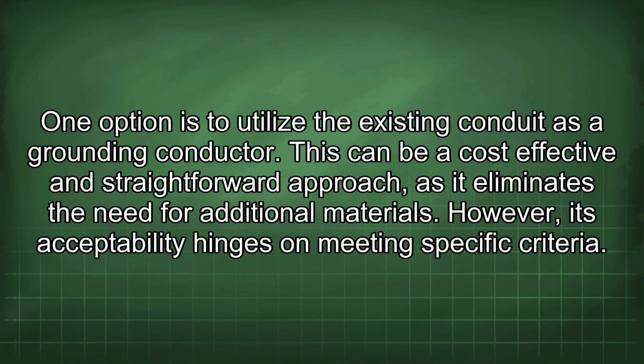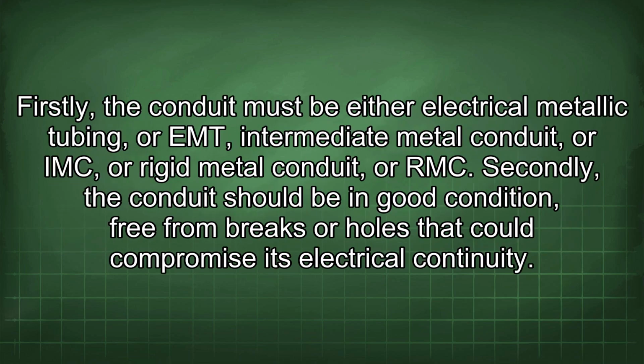This can be a cost-effective and straightforward approach, as it eliminates the need for additional materials. However, its acceptability hinges on meeting specific criteria. Firstly, the conduit must be either electrical metallic tubing, or intermediate metal conduit, or IMC, or rigid metal conduit, or RMC. Secondly, the conduit should be in good condition, free from breaks or holes that could compromise its electrical continuity.